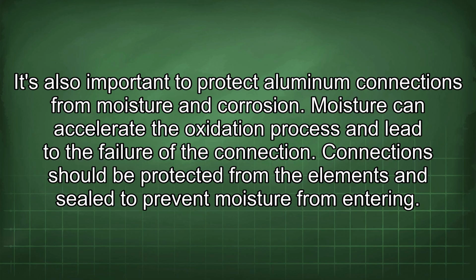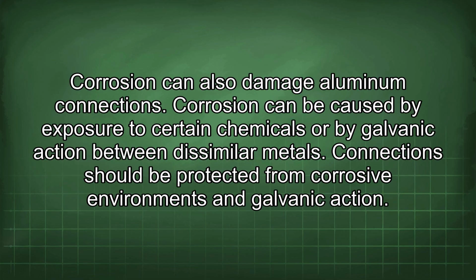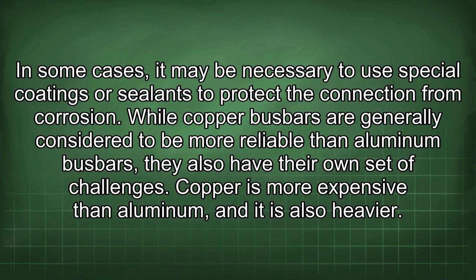It's also important to protect aluminum connections from moisture and corrosion. Moisture can accelerate the oxidation process and lead to the failure of the connection. Connections should be protected from the elements and sealed to prevent moisture from entering. Corrosion can also damage aluminum connections. Corrosion can be caused by exposure to certain chemicals or by galvanic action between dissimilar metals. Connections should be protected from corrosive environments and galvanic action. In some cases, it may be necessary to use special coatings or sealants to protect the connection from corrosion.